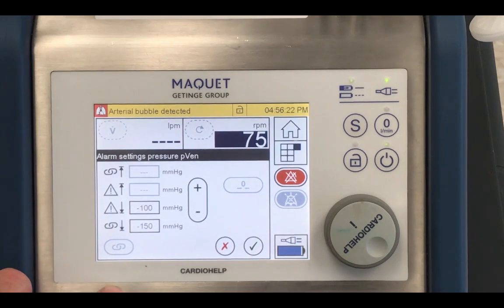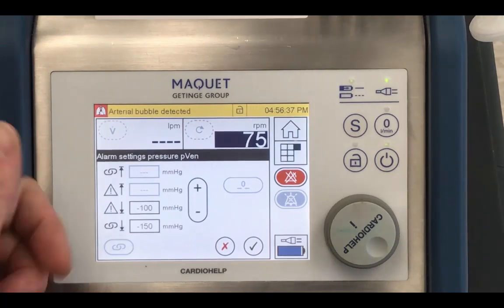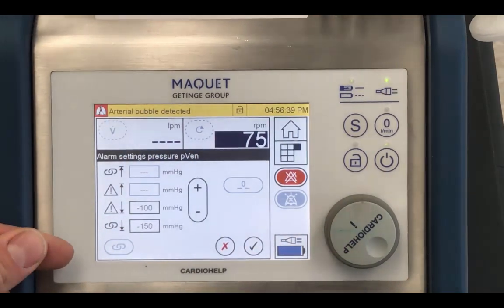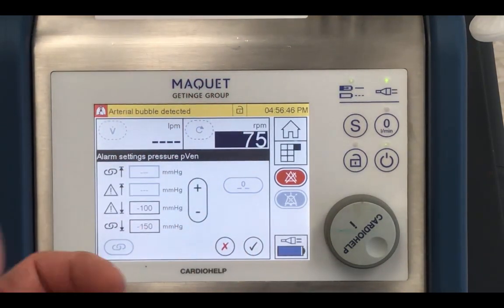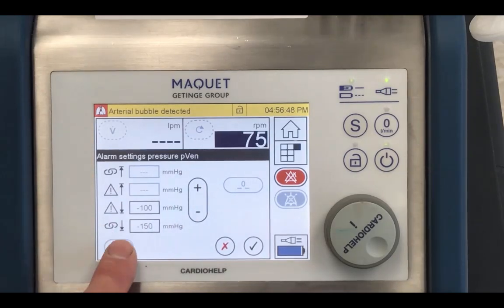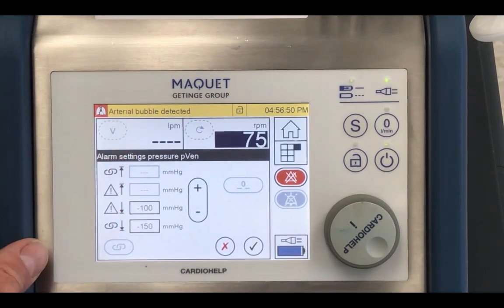to make sure that this doesn't get any lower than 150. If we want to turn that on, then we would press this button here, and it's grayed out. So that can sometimes be frustrating, that you think, I want to turn this on, but I don't know why I can't turn it on. And there's 2 things to look for. Does the system even know you're plugged into anything? As in, is the connection on the back there that we looked at earlier nice and tight, and are you getting data from the venous line pressure? Because you can't set an intervention to a transducer that it can't find. That's one thing. So let's go check that.